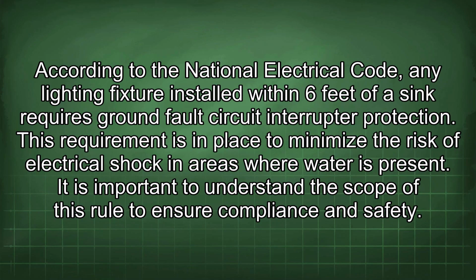According to the National Electrical Code, any lighting fixture installed within 6 feet of a sink requires ground fault circuit interrupter protection. This requirement is in place to minimize the risk of electrical shock in areas where water is present. It is important to understand the scope of this rule to ensure compliance and safety.